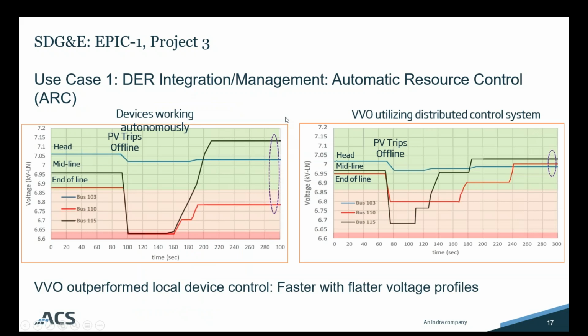So with that, we have two different charts here, and the way you can read them is time comes along the x-axis, and we are modeling 3 different voltages on various points along the feeder. We have 1 voltage point at the head of the feeder, 1 towards midline, and 1 towards the end of the line. And as the time goes along, we trip right around 100 seconds, as shown on the left graph, which is right when the large PV trips offline.